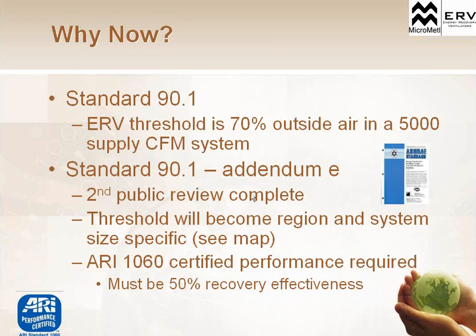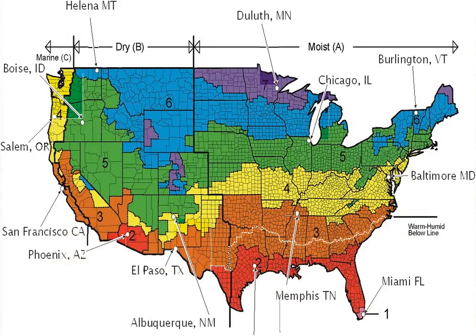So now, with the recent adoption, the second public review has been completed on addendum E. They've actually changed the threshold where ERVs are required. And they changed the threshold based on regions and size of the system. So not only based on CFMs in the system, but based on the region in the U.S. And that's specifically because of humidity requirements, because the second part to an ERV system is actually humidity. So they've broken that down into different regions, and they've added one more requirement: an energy recovery unit that's used must be at least 50% efficient, or 50% recovery effectiveness. And I'll explain what that means in a few minutes here.